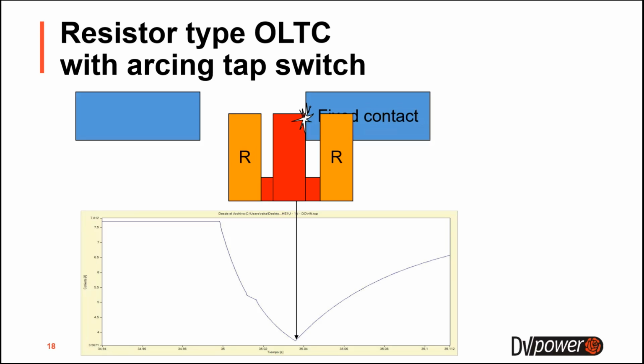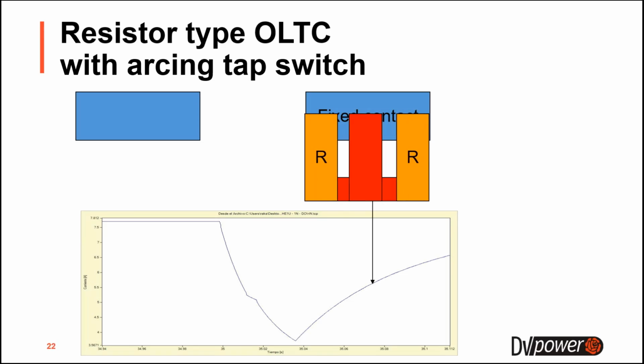And from that moment on, the current will increase and will get to the value which is proportional to the resistance of the next step position. So the current will not suddenly increase to the new value because of the inductance of the transformer, so it will take some time. That's why it is increasing with a ramp, not immediately. So this is typically what happens during the tap change operation.